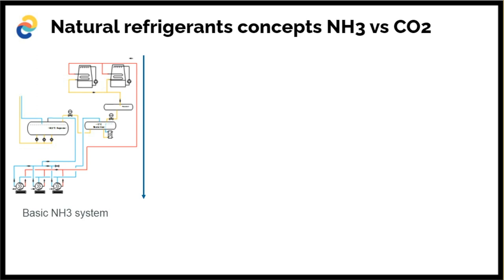We have here the basic NH3 system. It's a pump system. It's not with direct expansion, but it's still a pump system. That's always the safest solution there is. It's the cheapest solution. It's the safest solution in terms of being simple, reliable, energy efficient. However, there are circumstances where customers are not so happy with the amount of ammonia in it. There can be quite a lot of ammonia in it. And of course, with the DX systems, that could be reduced. But sometimes they don't want to have any ammonia in the cold store itself. So then we have to look to another system.